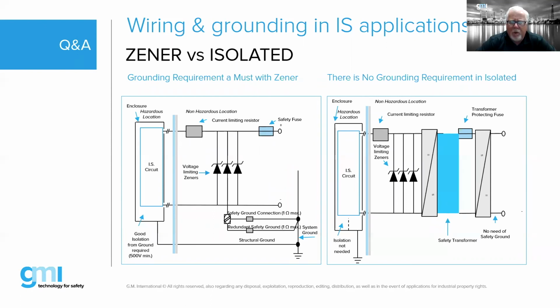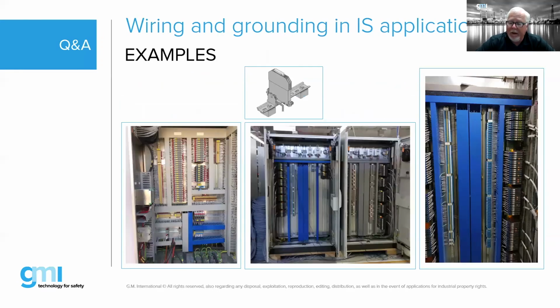Yeah. So it depends on the wiring regulations of where you are in the world. Typically, the screen on an IS circuit is going to be separate from your safety earth. It's going to be grounded to your normal earth, generally. But when we're talking about grounding of the barrier itself, that's the housing, which is tying in the Zener diodes to the earth tab, which is in turn tied into the DIN rail, which is tied into the grounding terminal, which is tied into a clean earth. But you also have to deal with the screens and drain wires and various other things, and where those need to be landed and terminated. So look closely at the wiring regulations within the country that you're in. But basically, we do have to ground those as well.